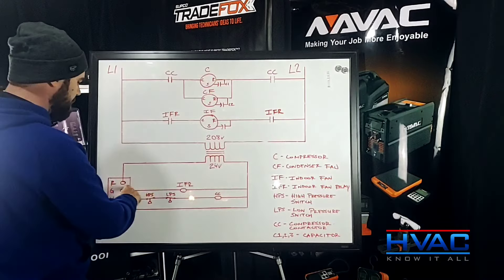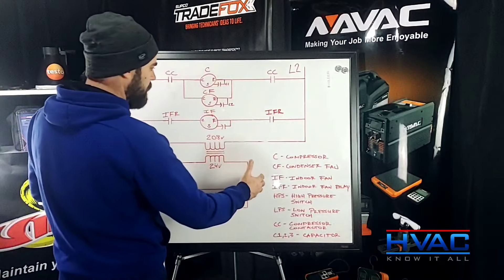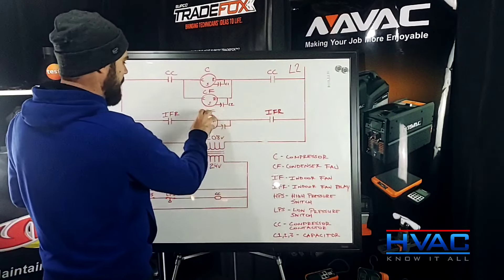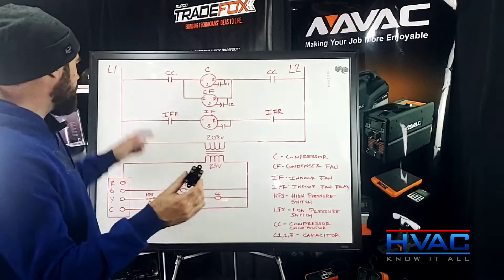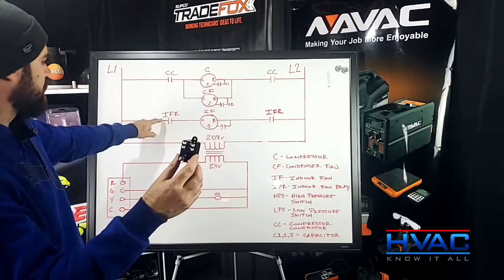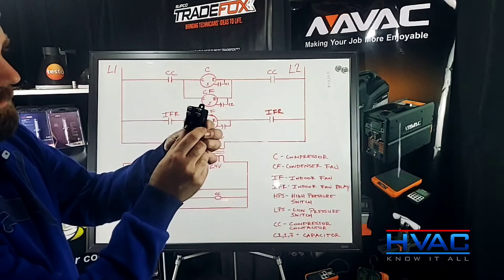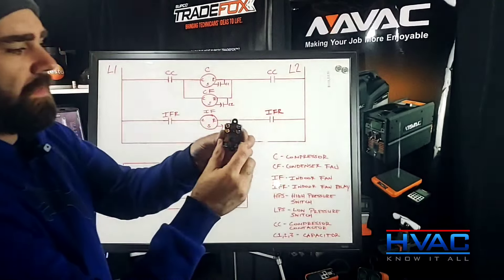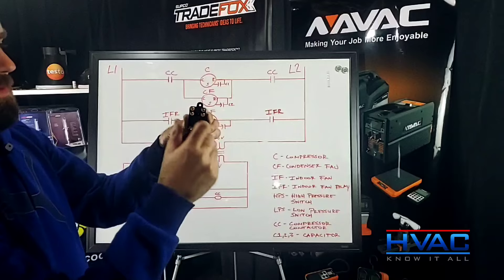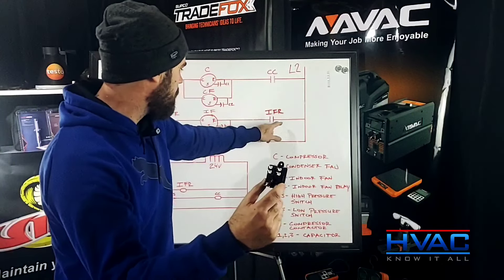So that's how I learned to read diagrams — I just put my finger on it, came across the legend, read what it was, and if I didn't know what it was, I would ask people. Once it's energized, came over here, closed, closed — we power this up. Back to this relay again: because we're coming in from two sides, this one coming in here is going to this terminal on this relay. Leaving is this terminal. On this side, we come in to this top terminal and then leave on the bottom terminal. So we energize here, these are open beforehand, as soon as we energize the path across these two closes, just like our line closes, and we start this motor up.